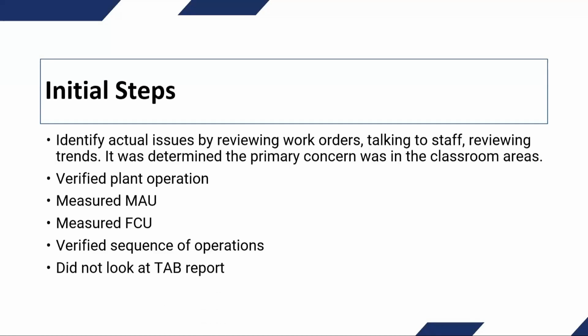One of the things that we did not do, that we typically will never do, is we didn't bother looking at the TAB report, even though it was provided. We typically won't look at the TAB report. If we've got a problem in a building, we find that it doesn't really do us any good. The only caveat to that is we will see who did the TAB. If it's an AABC company or a company we're familiar with, we typically will, out of courtesy, just contact them to let them know that we are going to be looking at a project that they completed.